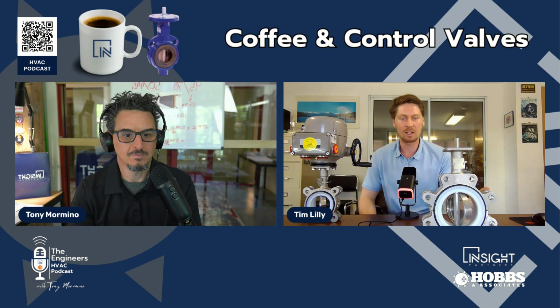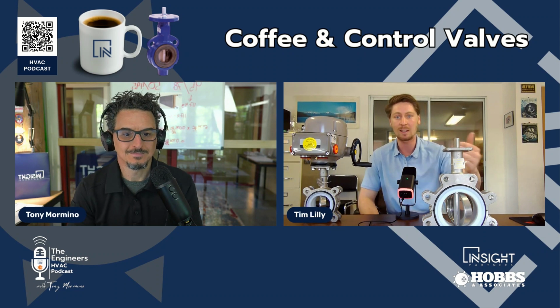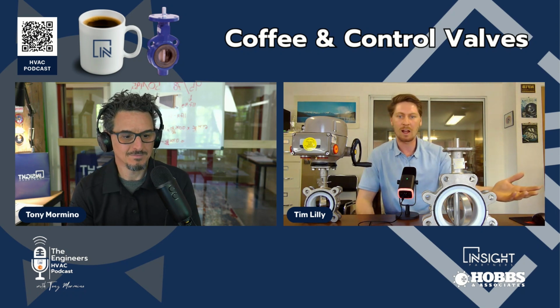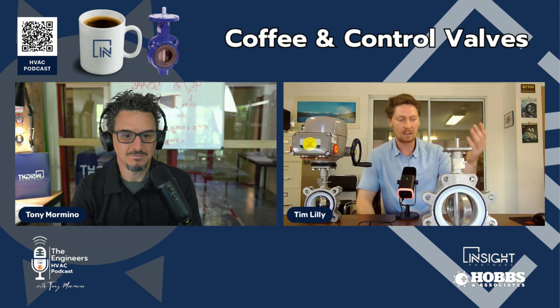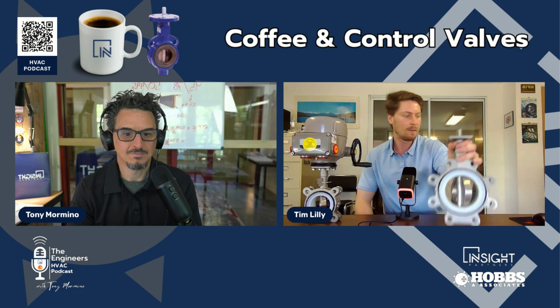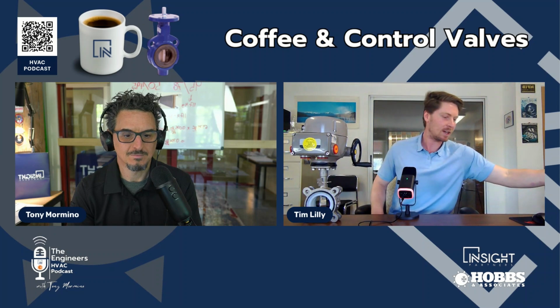The impetus behind the design is, can we teach a butterfly valve how to control? So you have the engineers at the brewery in St. Louis, at the brewery in Milwaukee, excuse me, saying, hey, we need these valves to modulate. We need them to hit their set point. We need them to stay right there. Can you do it? And so we first had to understand why you can't modulate with the butterfly valve in standard industrial applications. And so it turns out that if we re-engineer the disc, I'll do a little side by side.